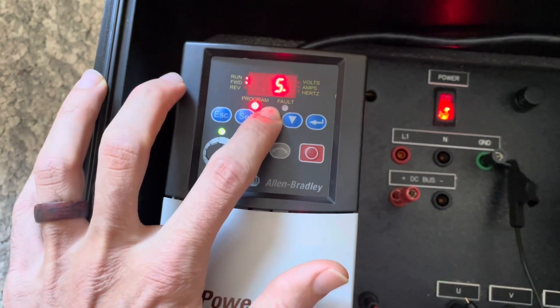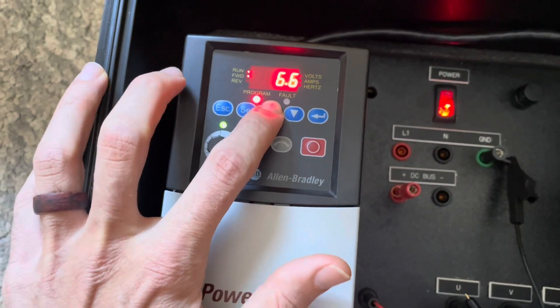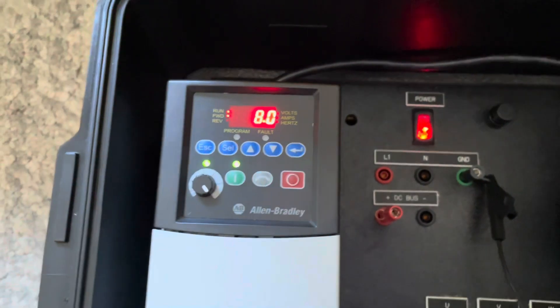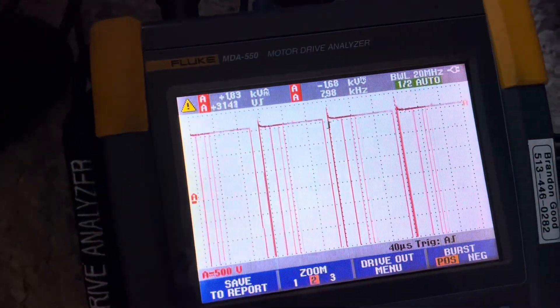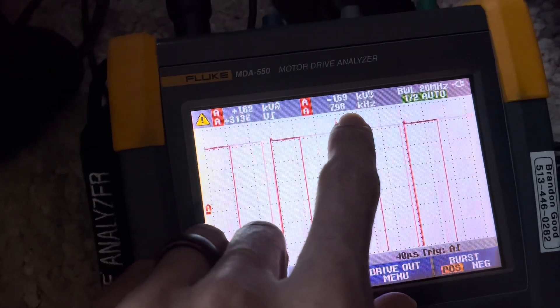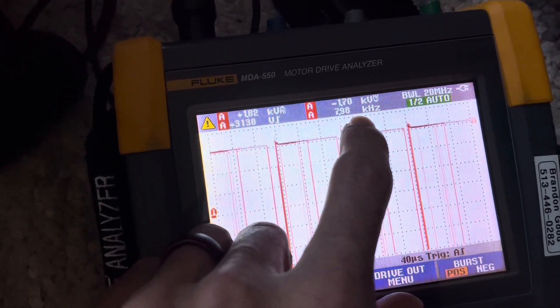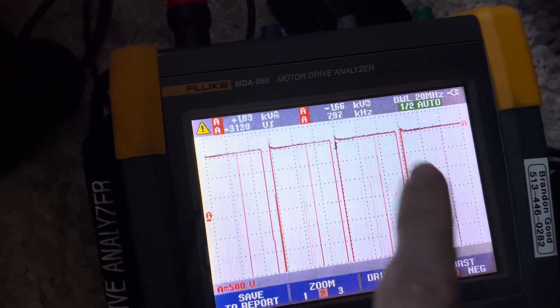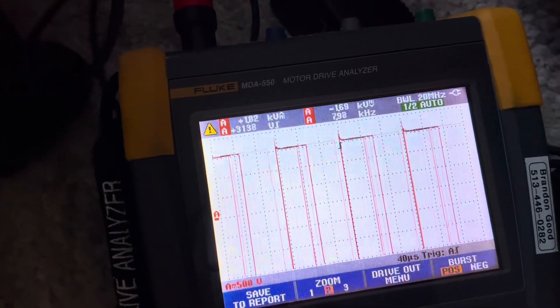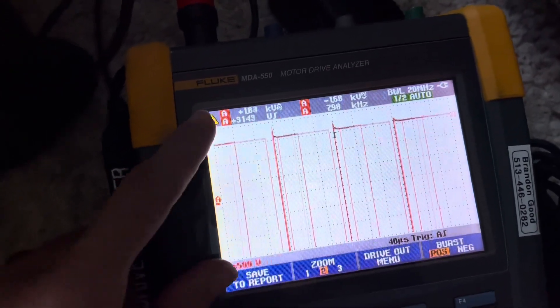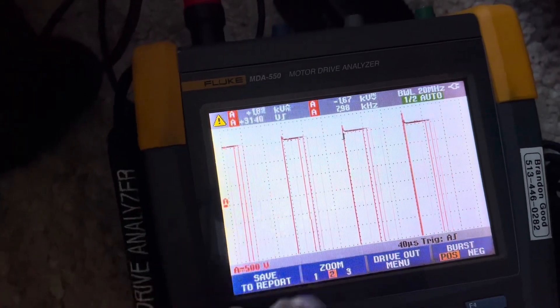Once it's programmed — and you can do this while the drive is running — if the audio weren't muted you would hear that dramatic shift in noise. Now you can see it reads 7.98 kilohertz, so almost 8 kilohertz, which is exactly what we wanted. So if you're programming a VFD in the field and want to confirm that changing the pulse width modulation setting is actually taking effect, this is how you do it with an MDA 550.